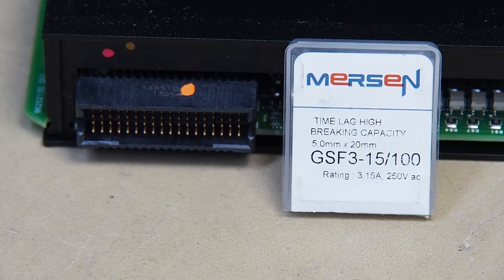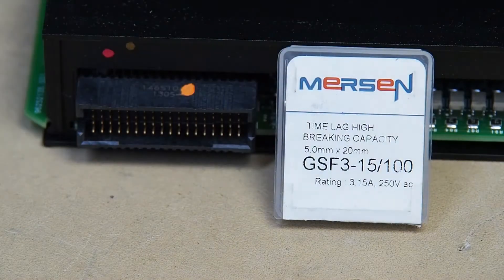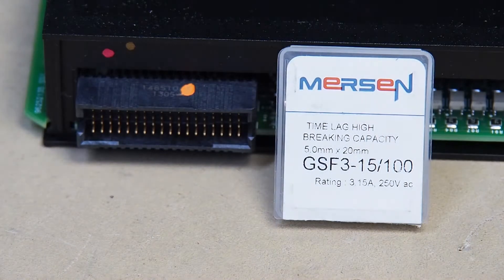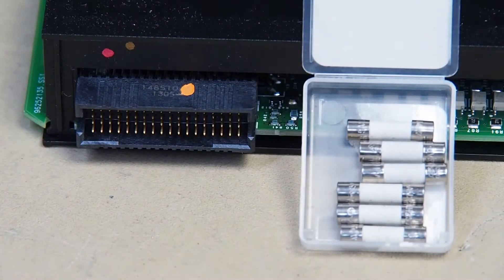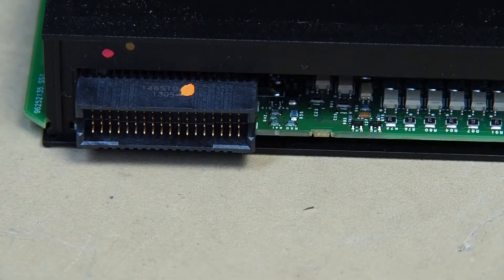Here's our package of fuses. The Mersen fuses - it's a GSF-15-100, which is a 5.0mm diameter, 20mm long, slow blow fuse. It's also called a time lag high. Those are the kinds of fuses that should be in your module to keep the warranty and to protect your module.